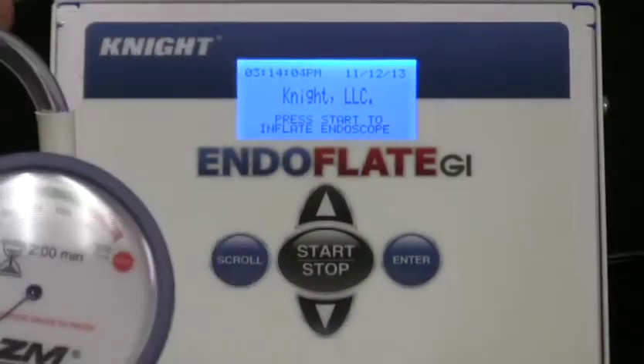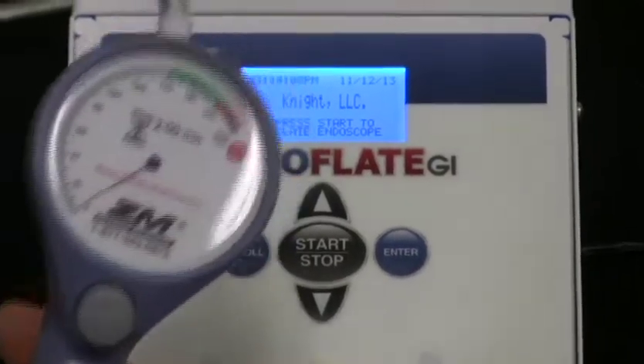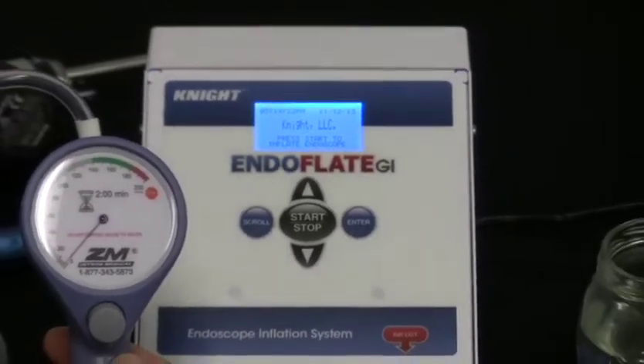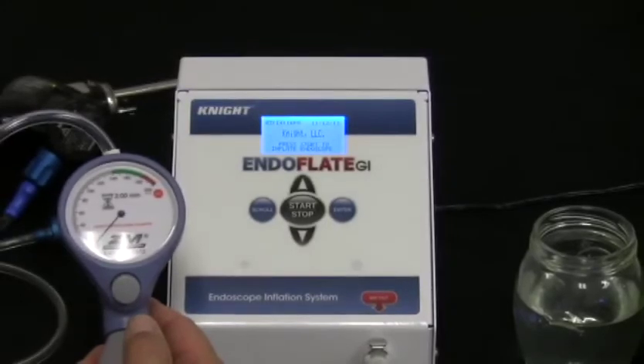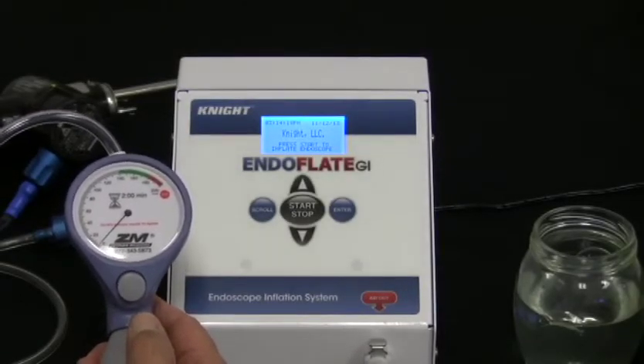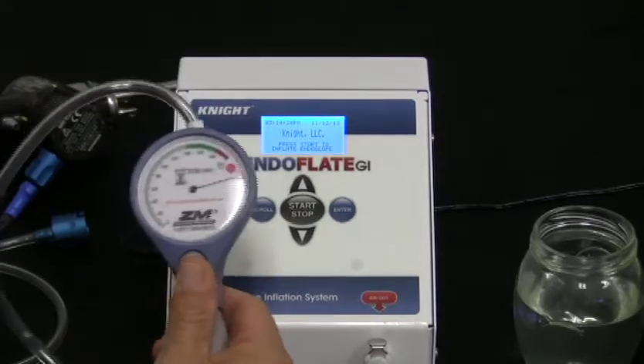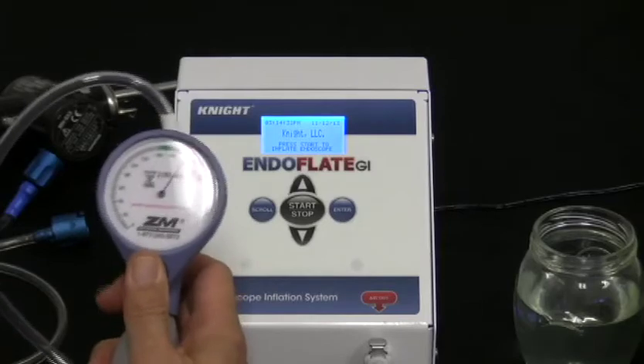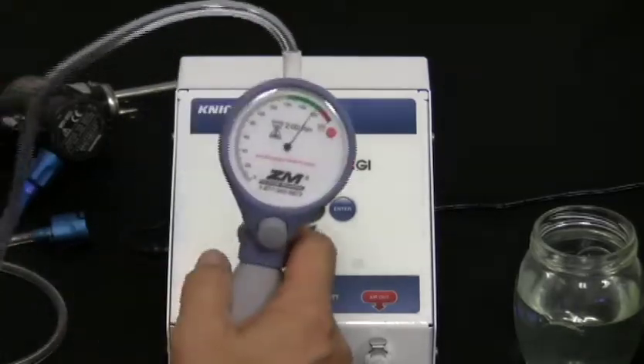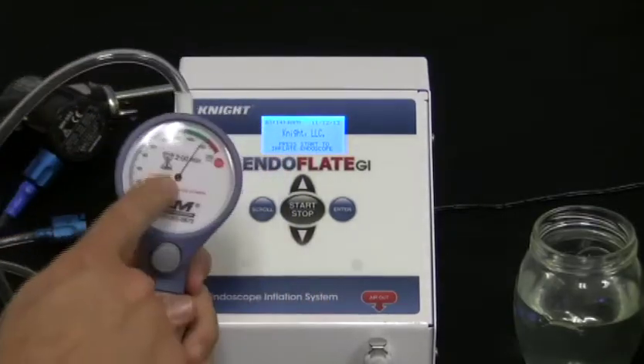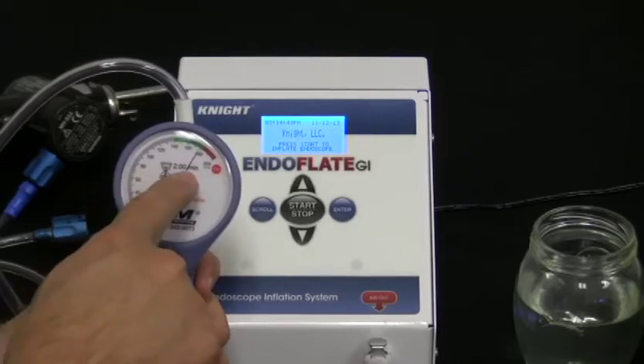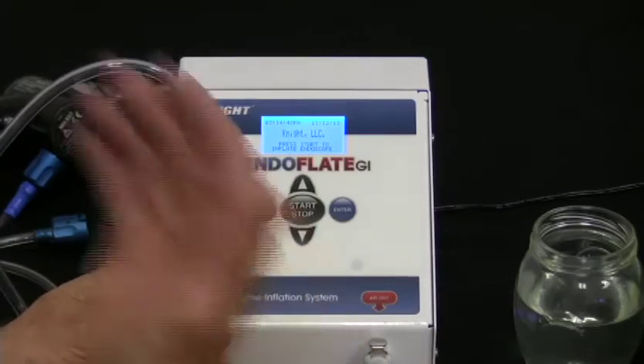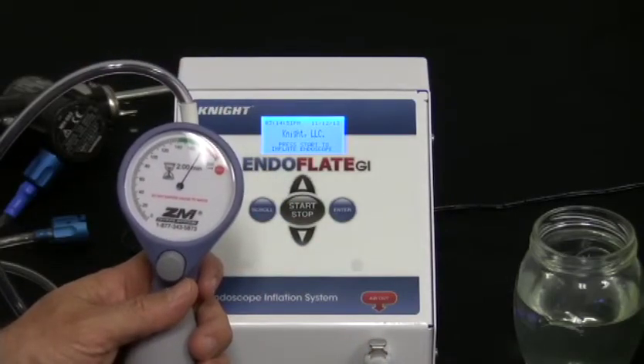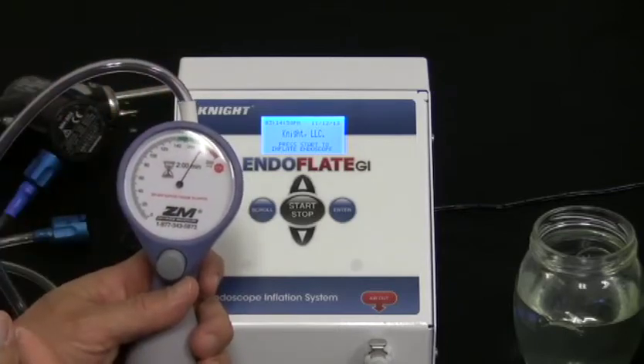So to give you a little further background on what our device is about, I think it's important that you reference a similar device, and that is the handheld leak tester. This one is made by a company called Zutron Medical, and very similar to a lot of other handheld leak testers that are made by Pentax, and Olympus has got them, and a number of other companies. Basically it's an inflation bulb, and by mechanical manual action I can inflate the lumens in the scope. I overinflated there. I've got to bring it down a little bit so you can see the gauge. By inflating this pressure bulb, now I'm looking at the gauge, and my device is telling me I've got to hold steady within the green for a period of 2 minutes. That basically tells me that that endoscope is leak-free, or at least to a point where I can clean it and the interior mechanisms within the scope won't be damaged.